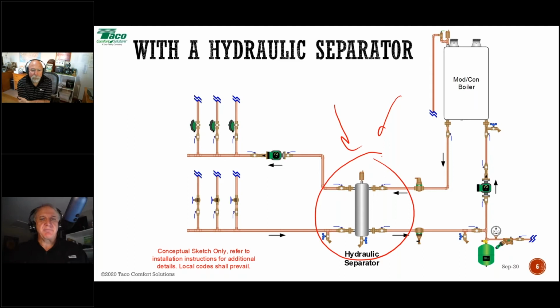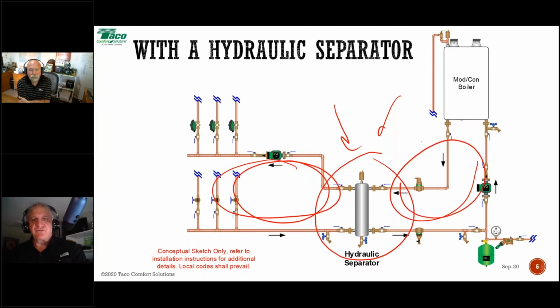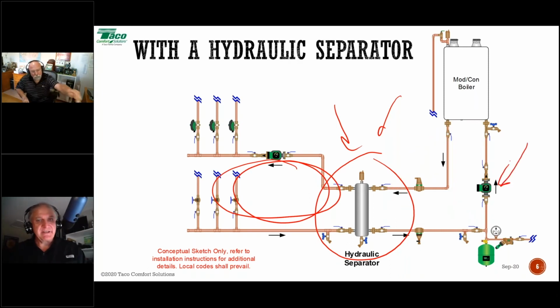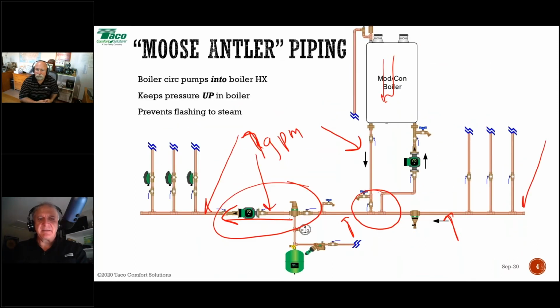Now, there are hydraulic separators that might have magnetic dirt separators built in, or air separation medium built in, potentially. But the biggest thing a hydraulic separator is going to do is make sure you have separation between this flow and this flow. It's going to make sure that they're completely separate. So flow through your delivery loop's not going to interfere with flow through your boiler loop. Even when using a hydraulic separator, of course, sizing your boiler pump properly is critically important, as is obviously sizing your delivery pump. When do you use a hydraulic separator versus this type of piping?